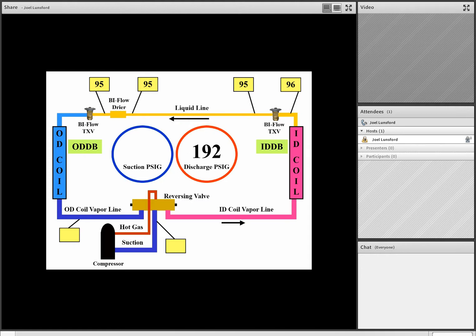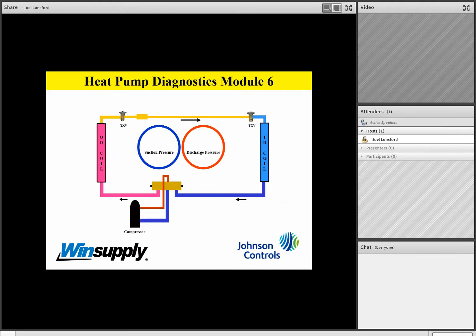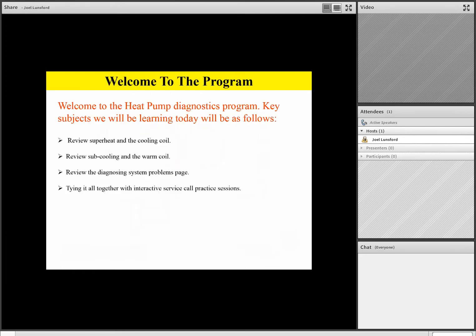So at this time, team, we've talked about superheat and subcooling. We've reviewed that. We've looked at our pressure temperature chart in Module 5. And so now we're going to continue with Heat Pump Diagnostic Module number 6. And we'd like to welcome you to that program as well. So this afternoon we're going to be talking about superheat and subcooling as well. Just as a quick review, we're going to review the Diagnostic System Problems page in your handout, and then we're going to tie it all together with some interactive service calls and practice sessions as we round out this program with session number 6 or module number 6.